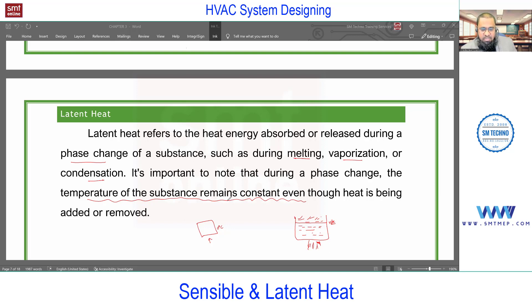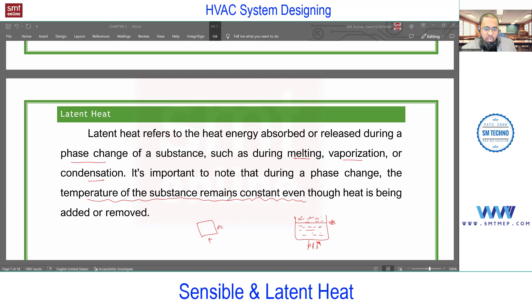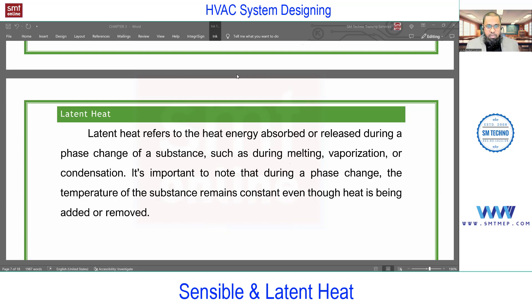For heat gain through ventilation — is it only sensible, sensible plus latent, or only latent? It is sensible plus latent. Why? Heat gain through ventilation means outside air. Air by default includes moisture. Dry air refers to sensible heat and moisture refers to latent heat, because that moisture needs to be extracted and condensed on the cooling coil to decrease humidity in the space. That condensation — change of phase — is latent. So sensible plus latent will be used throughout load calculation as per the type of source.